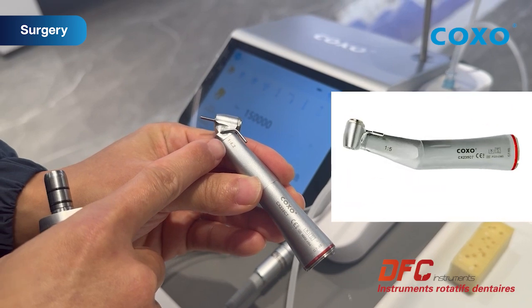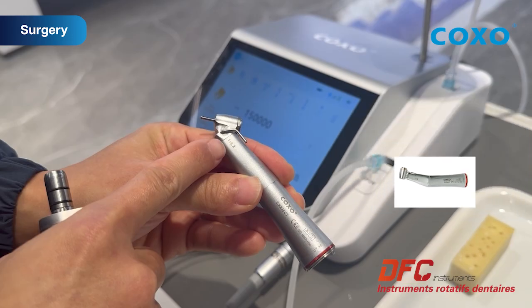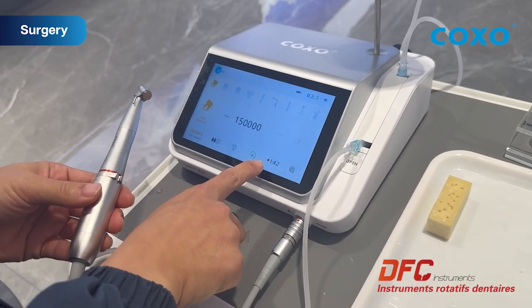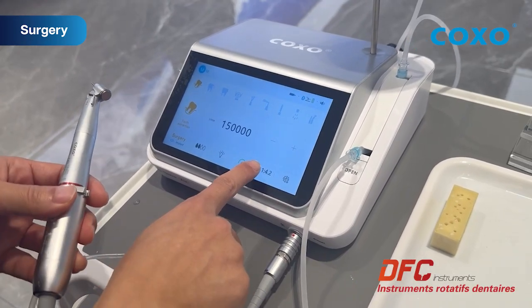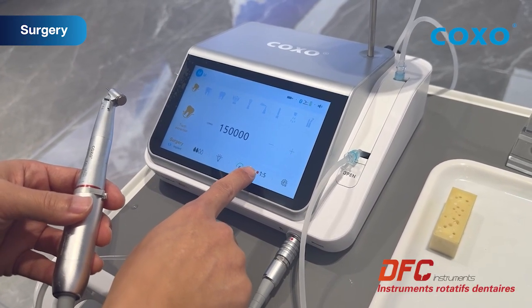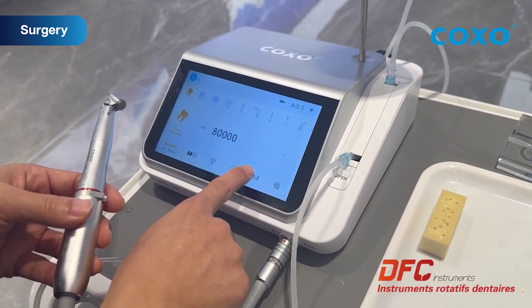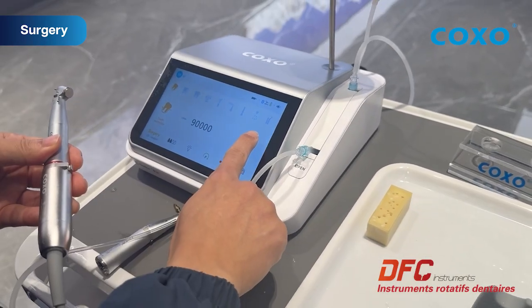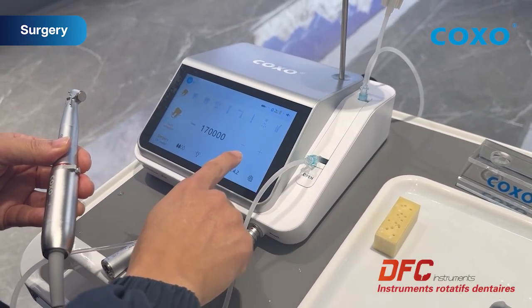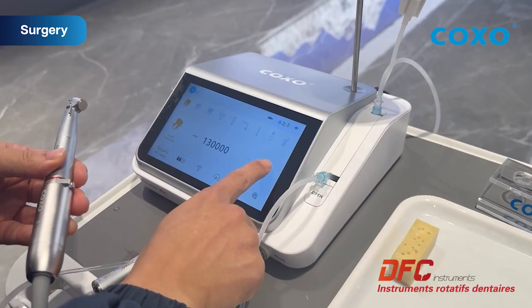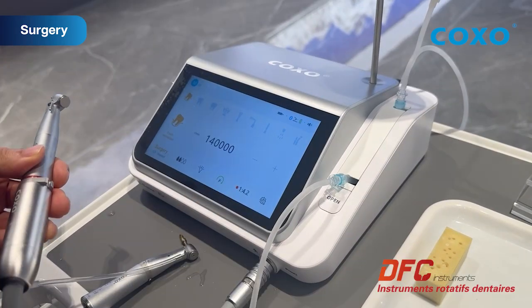On the other hand, the C-Sailor Air comes with a red contra angle model, C7.5S with a speed ratio of 1 to 5. Once installed, you must choose the correct ratio here depending on the contra angle. As you can see, the C-Sailor Air is compatible with many contra angles. The speed of the contra angle is adjusted by pressing the plus or minus touch keys. The surgical mode has several functions with default settings which can also be modified by the practitioner.